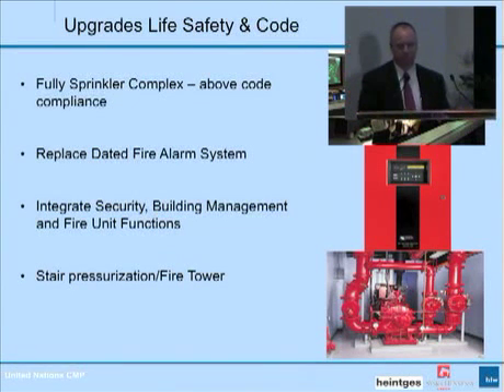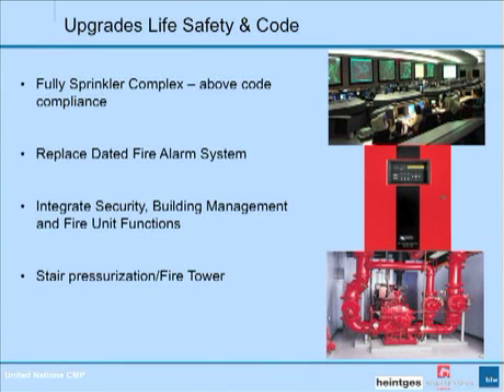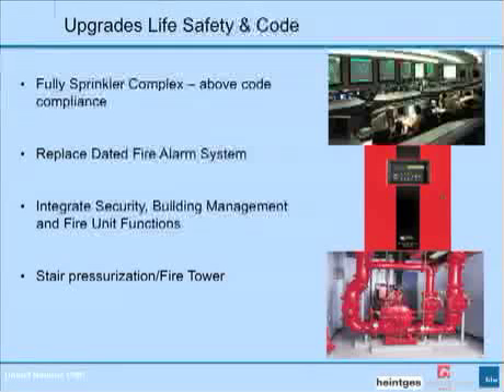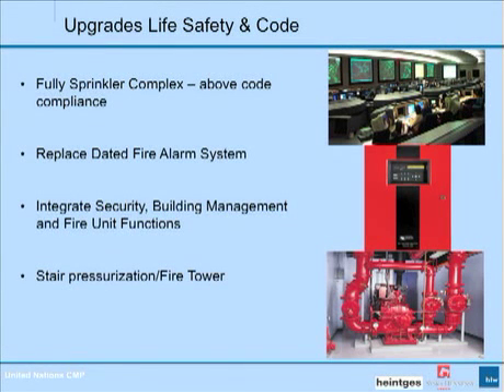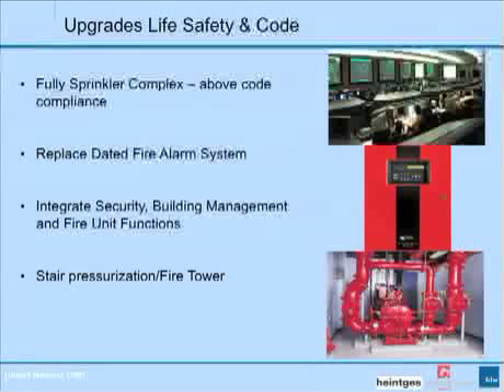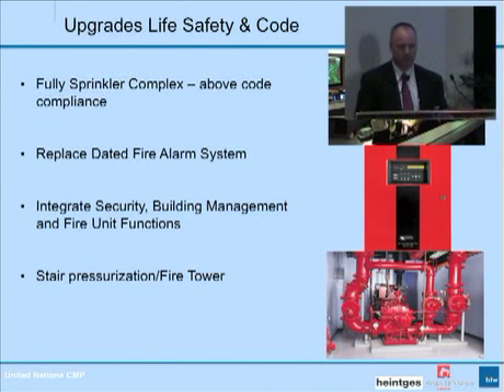And with this larger campus, we were able to incorporate location diversity in some of the key aspects of the life safety systems. So remote locations for fire command centers, for generators versus Con Ed services, and multiple fire protection services to the campus were incorporated into the design. We were also able to create an integrated command center for the security, fire alarm, and BMS functions for the campus. The campus also includes some above code items like fire tanks as well as a fire pump, stair pressurization as well as smoke-free fire stairs.